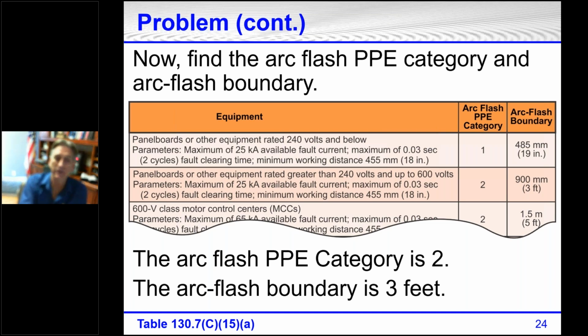And so then what's their choice? They go to this table. Well, they go to 70E. They look at this and they go, wait a minute, I don't know the maximum available fault current. I don't know the clearing time, because in order to know this information, you would have to do a system study. A system study is just a couple of clicks short of being able to print off a full arc flash label. And I know companies that are using these tables without knowing the parameters.